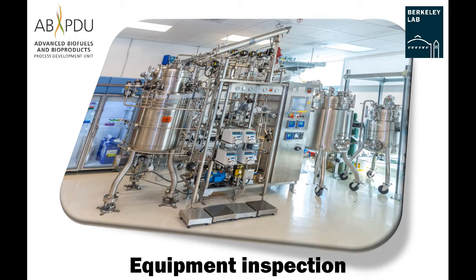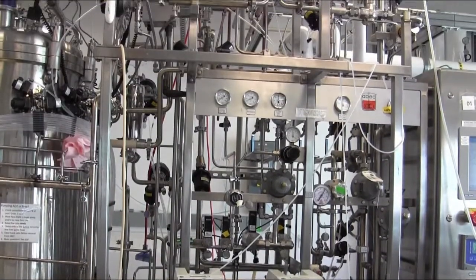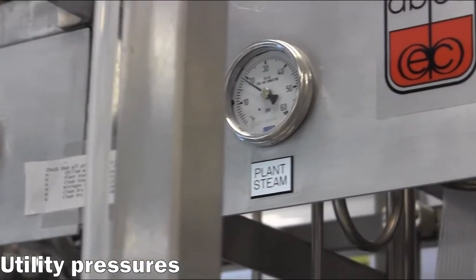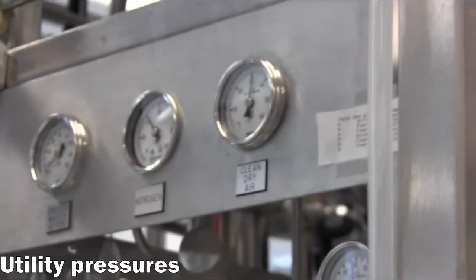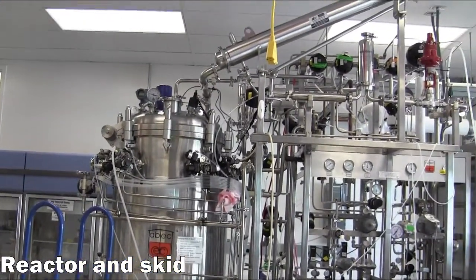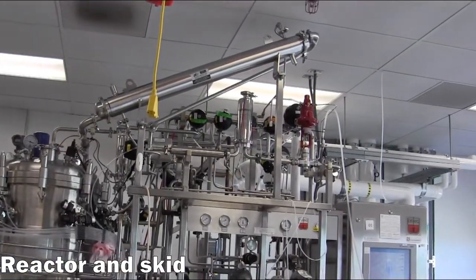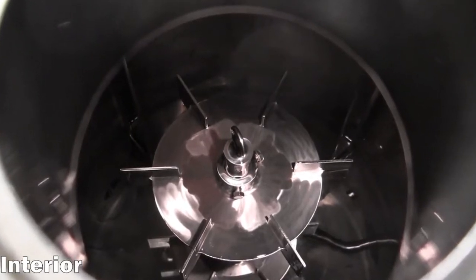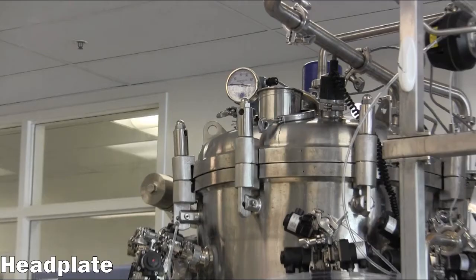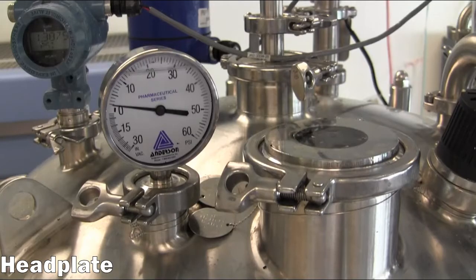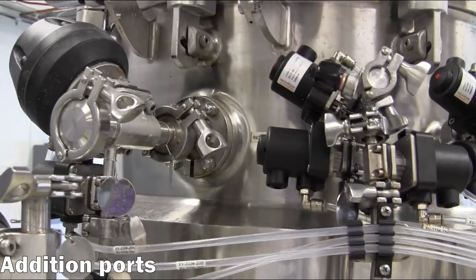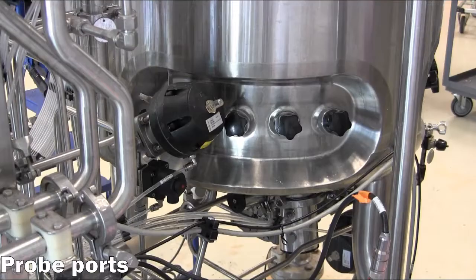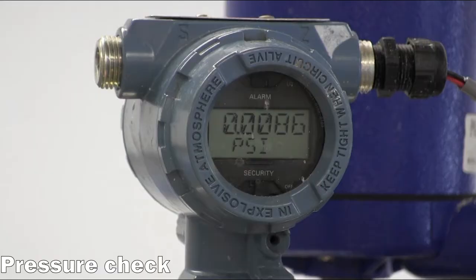Equipment inspection. Before we can proceed, we need to take some time to visually inspect the reactor skid. Start by checking utility pressure gauges for correct working pressures. Take a look at the outside of the reactor to spot any irregularities like loose connections from a previous run or dismantled parts, and make sure the interior is clean with no signs of deterioration. Check the head plate. The sight glass is removed often during preparation and cleanup. Both the hand valves and pneumatic valves on addition ports should be in the closed position, and probe ports should be sealed. As a final check, there should not be any residual pressure on the vessel.